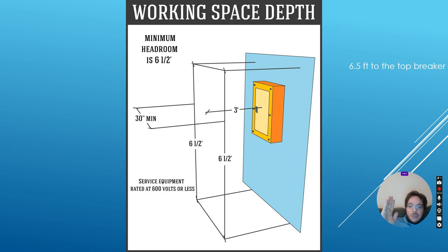Now, first thing is when you get your electrical panel, you want to keep at least a 3 foot working distance from the panel. So from the panel door fully closed, we want at least 3 feet in the horizontal direction. In Canada, it's 1 meter, and then we want to keep at least 30 inches left to right from the center of the panel. If the panel is wider than 30 inches, then we want the width of the panel. So this should be able to keep the door open at 90 degrees. Now, the top breaker on the panel should be no more than 6.5 feet from the ground. That lets almost anybody turn off all the breakers.